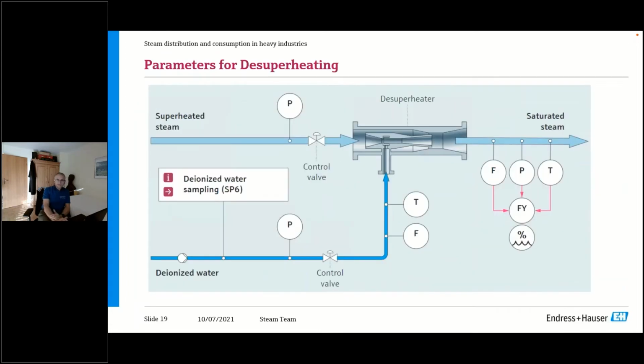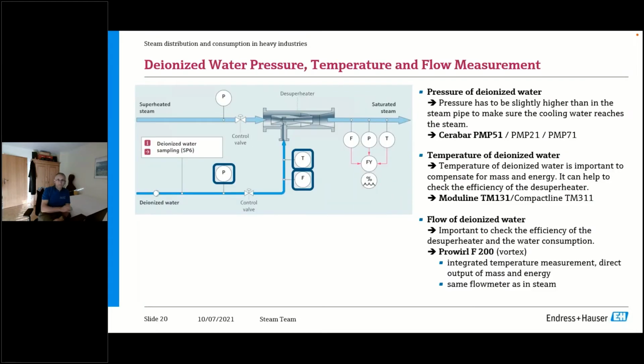But what is not so easy is creating an energy balance across such a device. So for that purpose, what is ideal, especially at the outlet, I recommend to measure pressure, temperature and the dryness fraction. We're going to come to that. Why? I would measure the pressure of the superheated steam coming in and the pressure, flow, and temperature of the deionized water coming in. Also, the quality is very important, but we're going to cover that in our module 5 in the SWOS section.